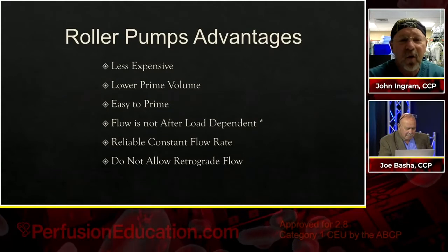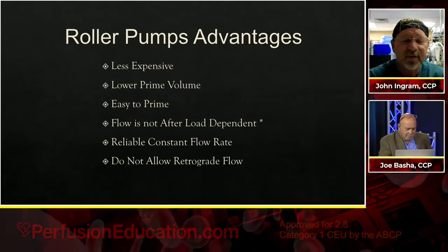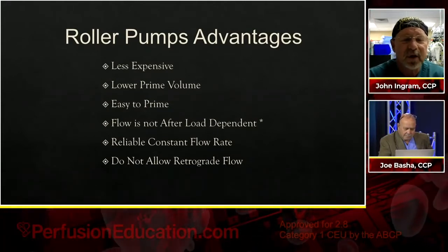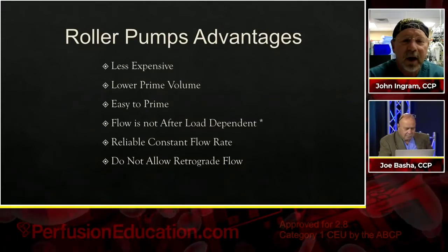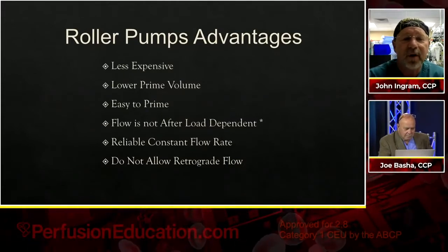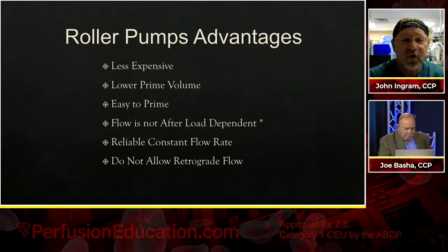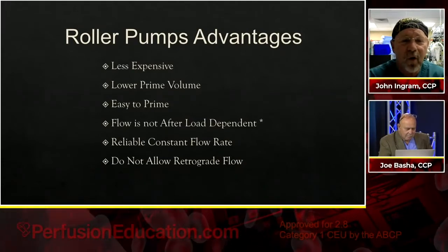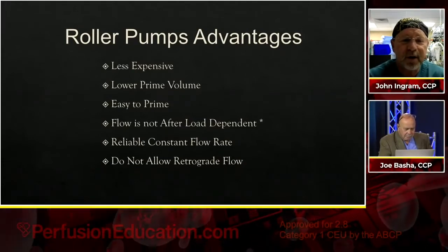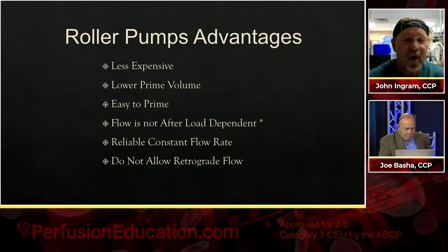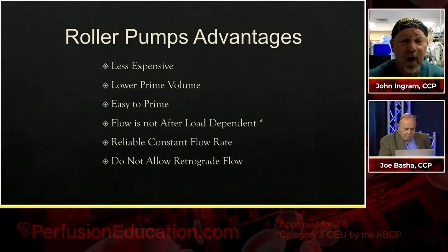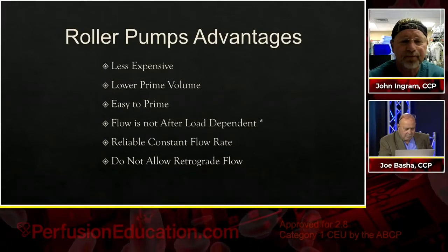So what are some of the roller pump advantages? Well, it's less expensive. It's really just a piece of tubing. It's definitely lower prime volume than a centrifugal pump. It's just the tubing length that's going through the roller head. It's definitely easy to prime. You basically can turn on a dry pump line and prime it right through, and it primes almost immediately.